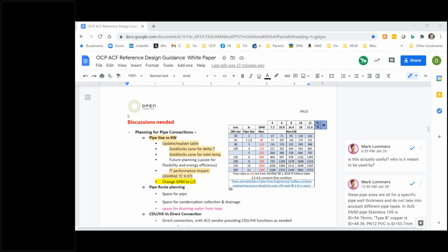So this basically says, using a limit on flow rates, maxing out at a flow rate for a given pipe size, at this pipe size and a given delta T, which is across the top, the theoretical max that you can pull in kW. So it's a ballpark, right? You say, okay, I've got a DN 100 pipe, and I'm going to have a 6 degree C delta T. I could potentially get 332 kW. Now the actual number is going to be somewhat different and lower than that, based on actual performance and a whole bunch of other factors, but that does give you an idea of what you can implement. So that's the intent of this chart.